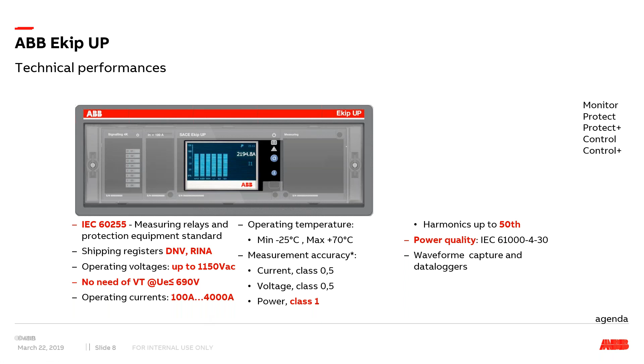It has a high accuracy class as well. In terms of current class, that's 0.5. In terms of voltage class, that's 0.5. And in terms of power kilowatt accuracy class, it's class 1. It is able to measure up to the 50th harmonic, and it is able to provide waveform captures and data logger functionalities too, in addition to the remaining items it is measuring. In terms of current, it can measure up to 6,300 amp. There's a typo here for 4,000. There's an advancement now that it can do up to 6,300 amp as well.